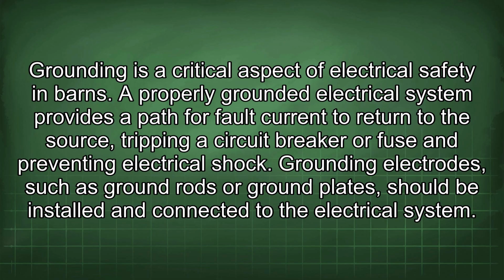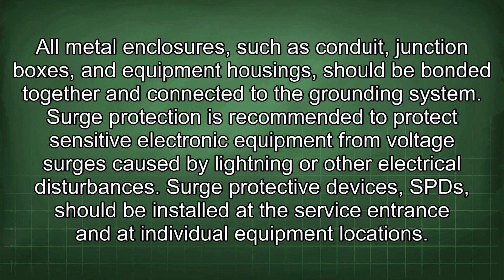Grounding electrodes, such as ground rods or ground plates, should be installed and connected to the electrical system. All metal enclosures, such as conduit, junction boxes, and equipment housings, should be bonded together and connected to the grounding system. Surge protection is recommended to protect sensitive electronic equipment from voltage surges caused by lightning or other electrical disturbances. Surge protective devices, SPDs, should be installed at the service entrance and at individual equipment locations.